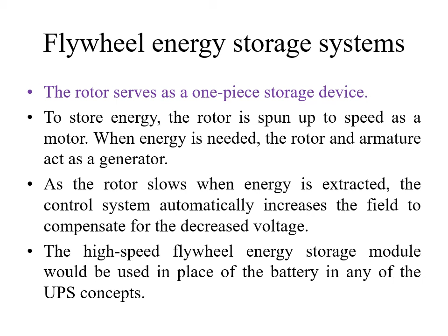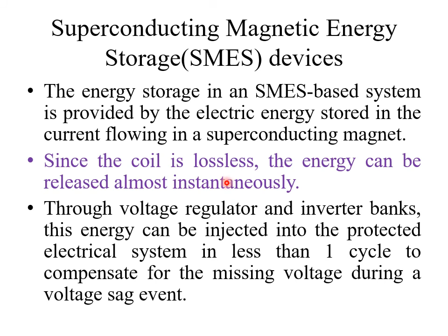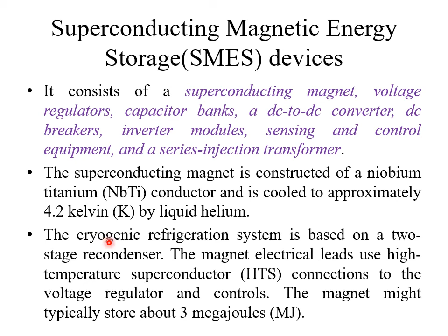Superconducting magnetic energy storage devices can also provide a solution for voltage sag. Here the coil is lossless, therefore the energy can be released instantaneously. The superconducting magnet is constructed with a niobium titanium conductor, and it is cooled to approximately 4.2 Kelvin by liquid helium. And this is how the superconducting magnet is constructed.